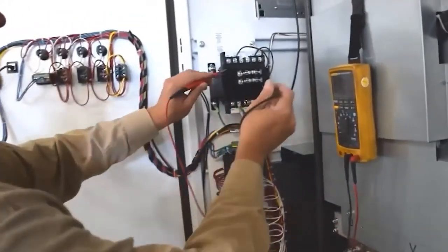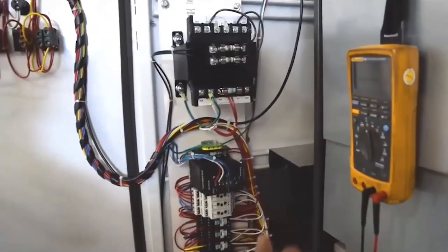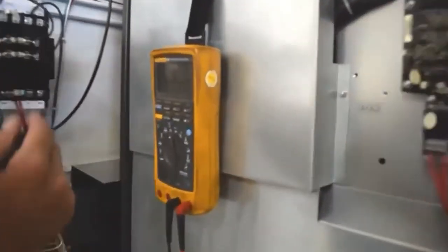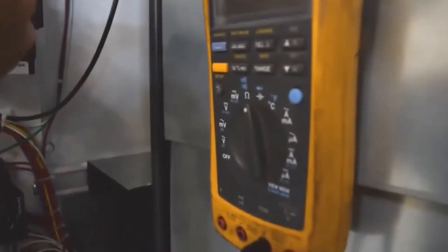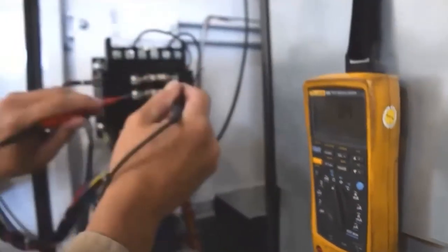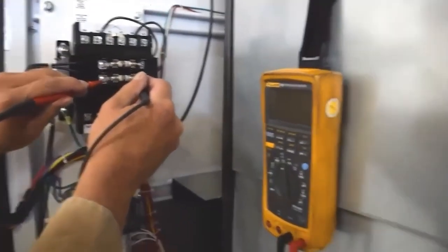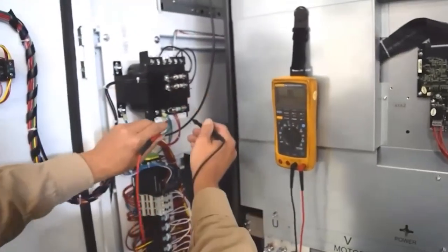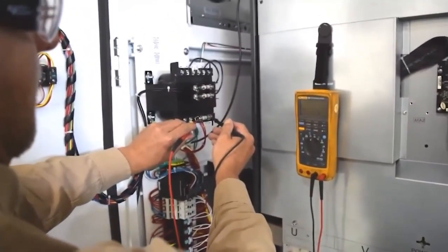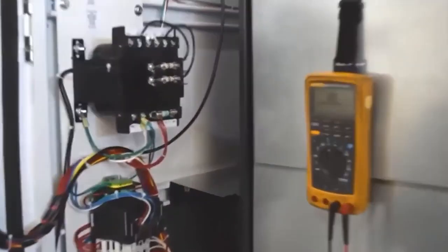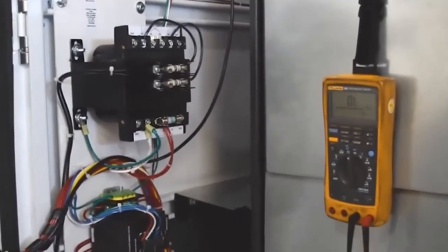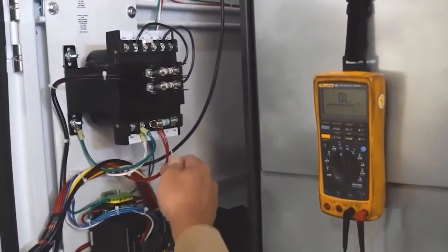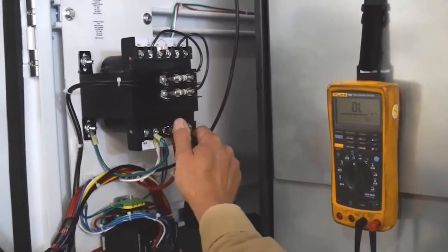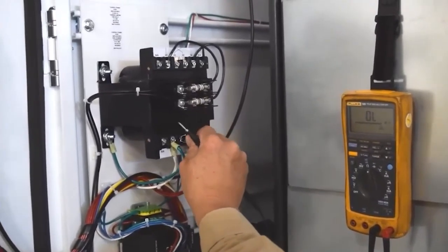I'm going to get my meter set up, put my meter in ohms, and then I'm going to measure the primary of my control power transformer, and the secondary of my control power transformer. Now, keep in mind, I didn't pull them out. If I see a reading that looks unusual, I'll pop the fuse out of the socket, and then I'll measure it isolated from everything else.